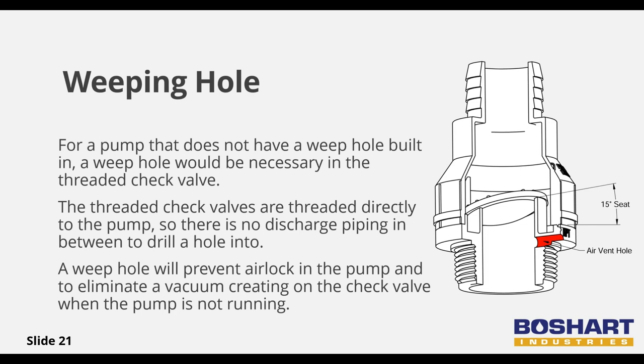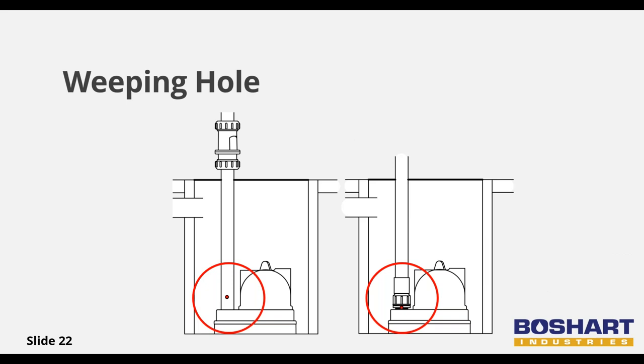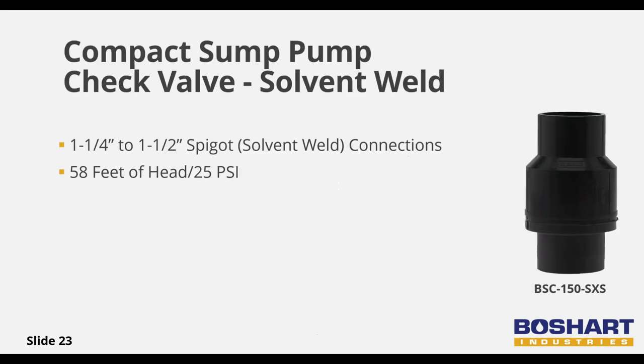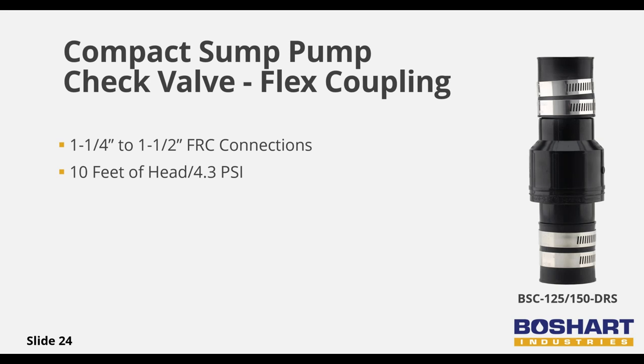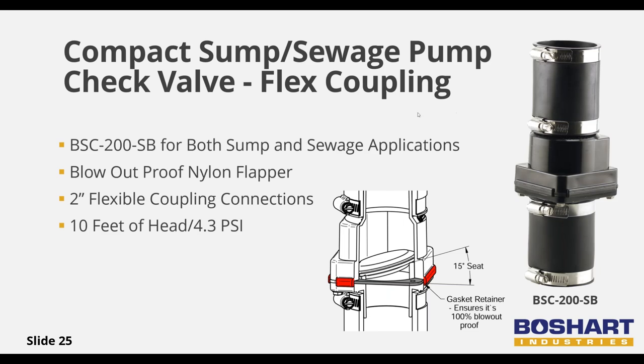Weep holes are often already installed in the discharge casting of many pumps, but some require a weep hole to be drilled into the line before the check valve — check with the pump manufacturer if unsure. Compact check valves with solvent weld inlets do not come with flexible coupling configurations, so thrust blocking is not required and the pressure rating is 25 psi. Compact check valves with flexible rubber coupling inlets also have flexible rubber coupling outlets; the maximum pressure rating is 4.3 psi and these need to be thrust blocked.